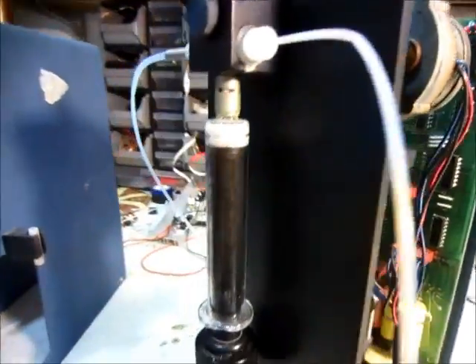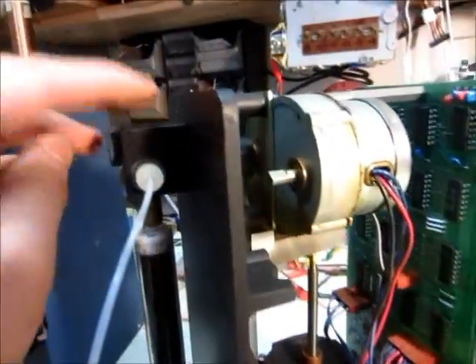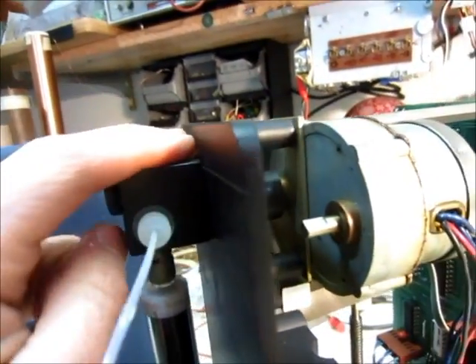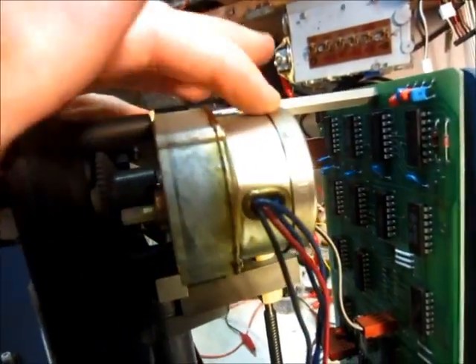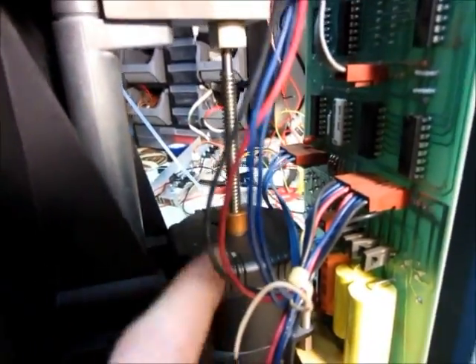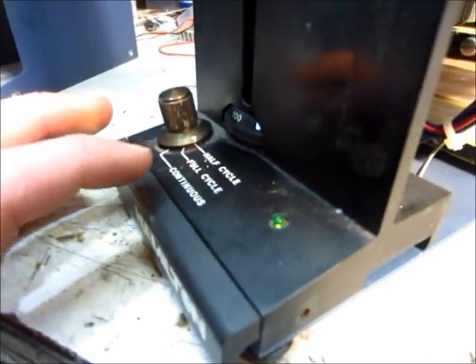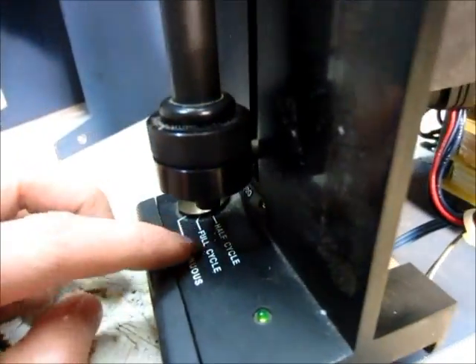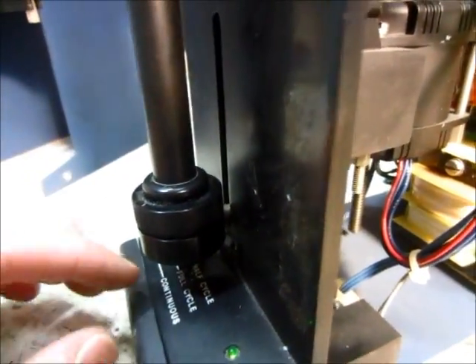So it's pretty simple inside - we've got the syringe, and this is actually a valve up here, not a check valve. This motor runs the valve, and this motor runs the screw up and down. I finally figured out how to turn it on, which isn't very obvious - push this down and it starts. But I have it on half cycle right now, so it just goes down half cycle.